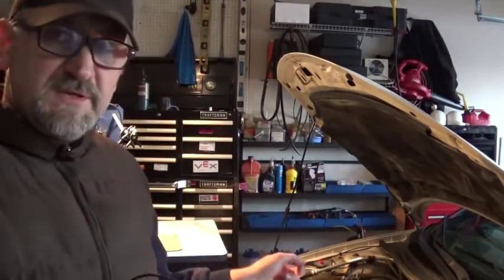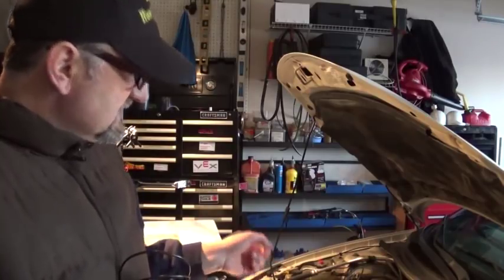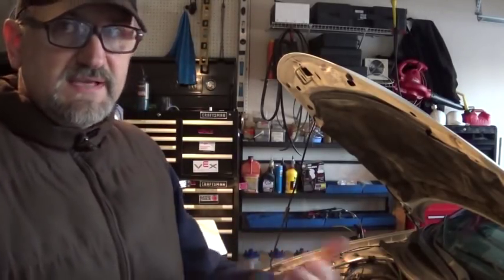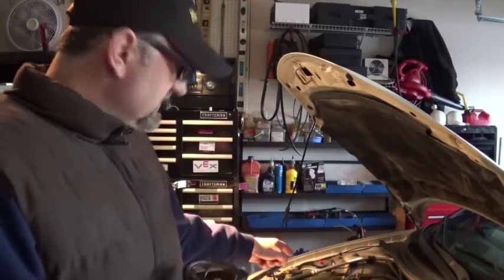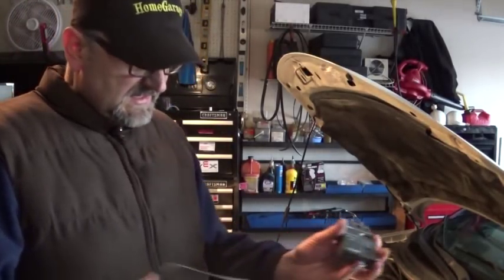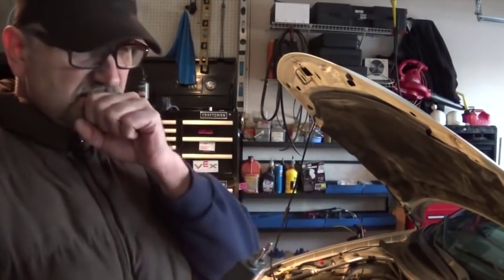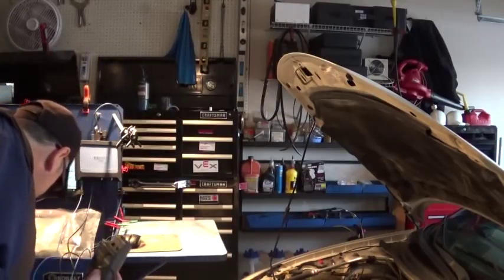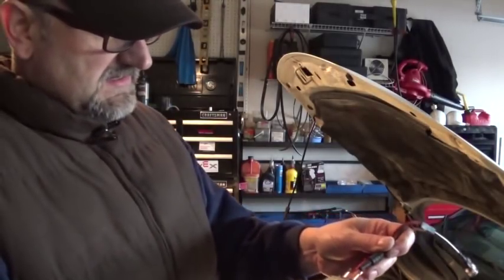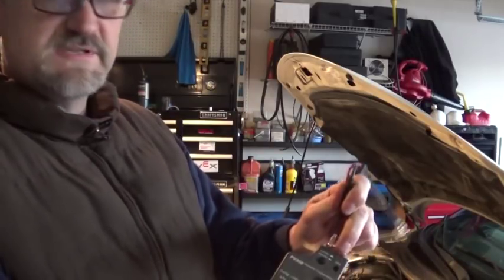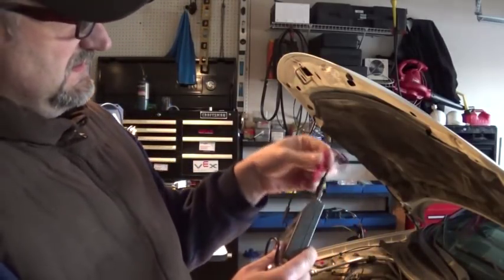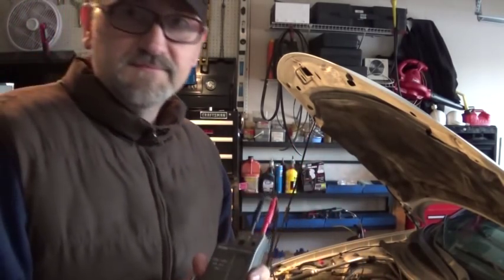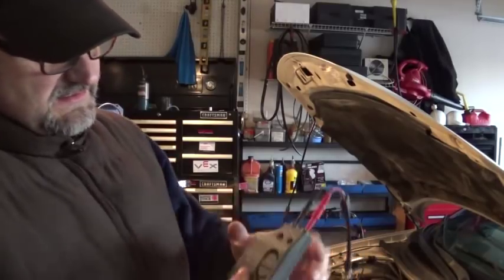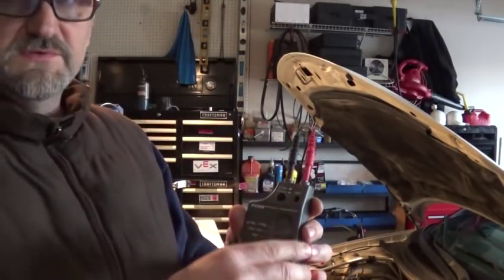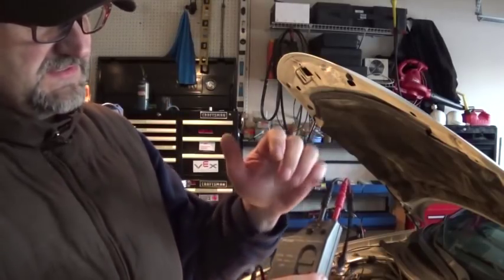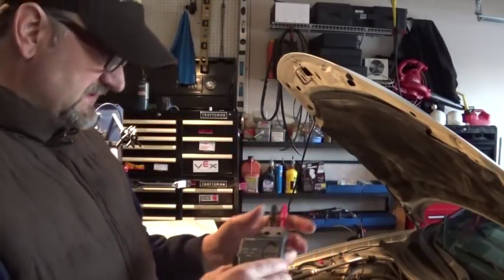Now on the Pico scope, on the WPS 500, it's kind of similar, but it's actually times 10. So 10 millivolts is equal to 1 psi. That's it, on setting number 1. Okay, so on this one, for my scope, I have to put an adapter for the BNC, because this is a banana adapter. This is the positive, this is the negative side. This one will not calibrate automatically. Here is your zero dial to zero it down, but once I set it where it needs to be, it pretty much stays there. So that's not an issue at all.